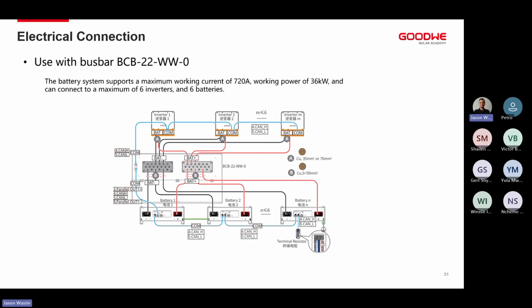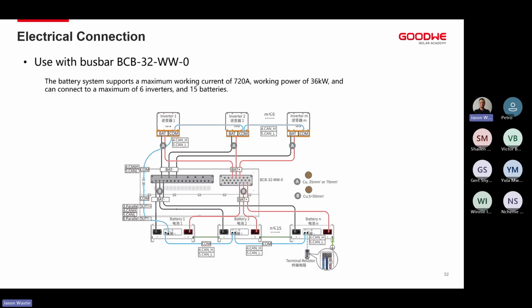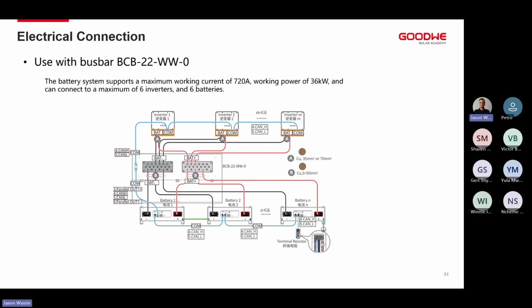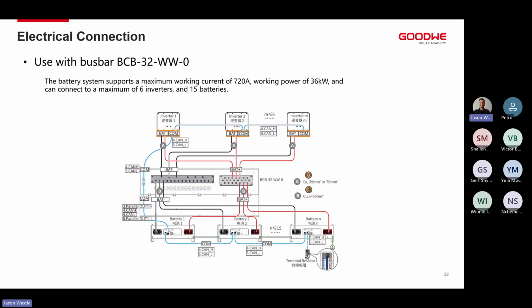So we've got 2 different busbars when it comes to the GoodWe side of things. We've got a BCB22 and BCB32. This is what we use to connect to the ES Uniq series. The difference between the 2 is just the physical size of them. So you'll see this one can connect a maximum of 6 inverters and 6 batteries. The BCB32, 6 inverters and 15 batteries. So we can then increase the working power to 36 kilowatts or 720 amps. So even if we're using one inverter and we need to increase the working power on the batteries, we can then use a busbar and get more out of the batteries themselves.